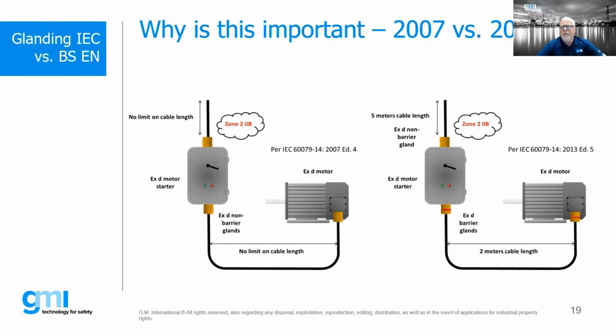If we look at the slide on the right-hand side, we see that based upon the fact that now we're more concerned about the cable length, and that's the big deciding factor, we might have to use barrier glands as opposed to non-barrier glands based upon the new standard.